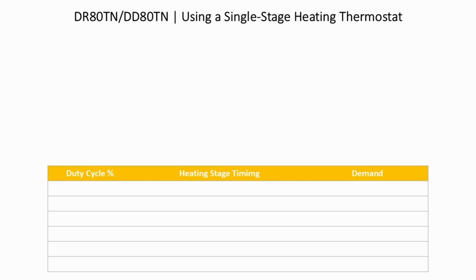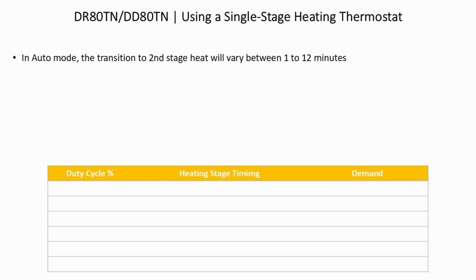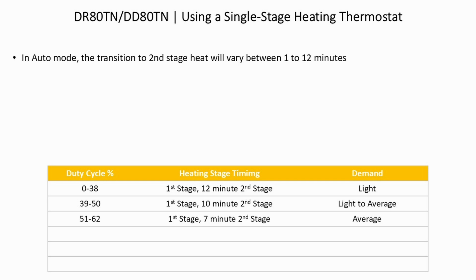The DR80TN and the DD80TN using a single-stage heating thermostat. In auto mode, the transition to second stage heat will vary between 1 and 12 minutes. For instance, if the duty cycle is 0 to 38%, first stage heat will operate for 12 minutes, then transition to second stage for a light demand. Between 39 and 50%, first stage heat will operate for 10 minutes, then transition to second stage, light to average demand. From 51 to 62%, first stage heat will operate for 7 minutes, then transition to second stage for an average demand. From 63 to 75%, first stage heat will operate 5 minutes, then transition to second stage. That is for average to heavy demand.